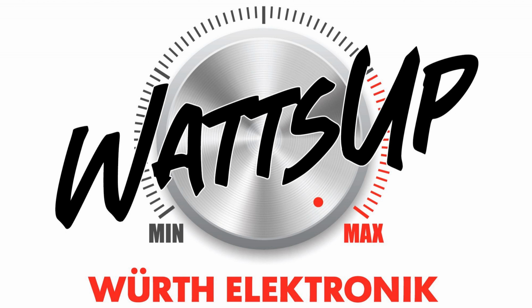So if we are focusing on decreasing the winding to winding capacity, it could happen that instead of putting primary and secondary above each other, we can put one winding and the second winding on the core separately from each other. It's a very good distance for safety margin as well. But what will happen? You decrease the winding to winding capacity, but you increase enormously the leakage inductance.